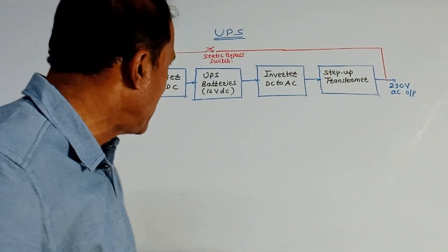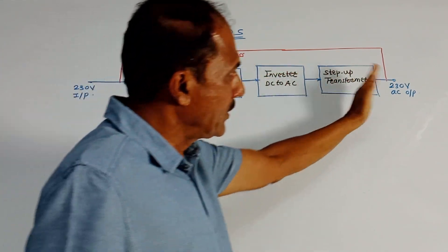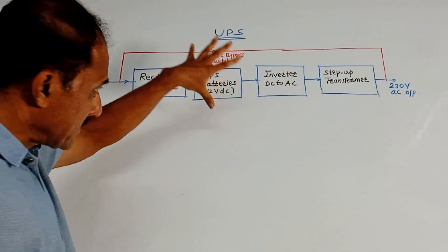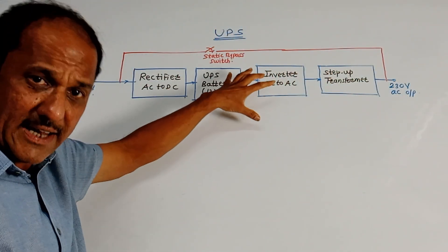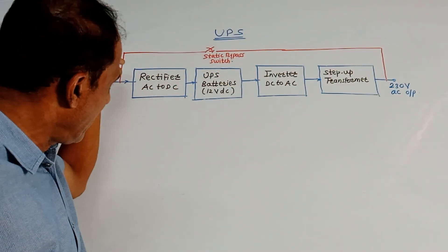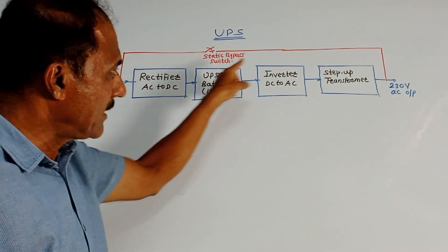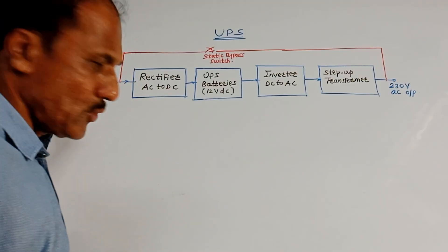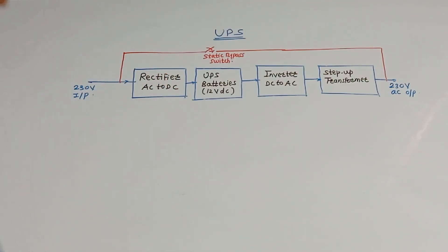Whenever AC mains fails, due to this block diagram you are again getting 230 volt AC at the output side. If for some reason this UPS fails, then one static bypass switch is connected — so you can bypass all these blocks and the appliance is directly connected to the 230 volt input. This is about the block diagram of UPS.